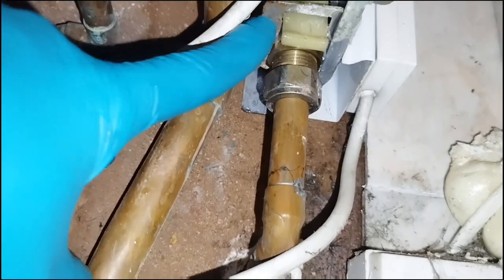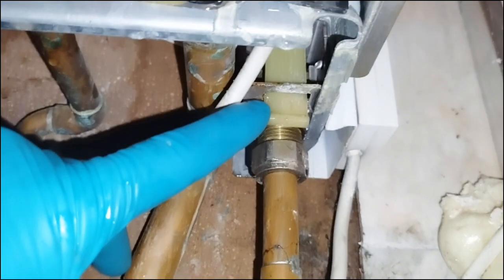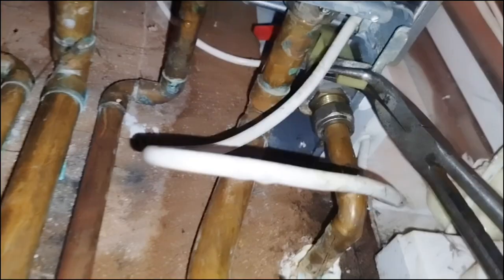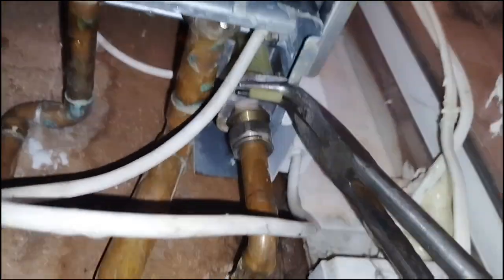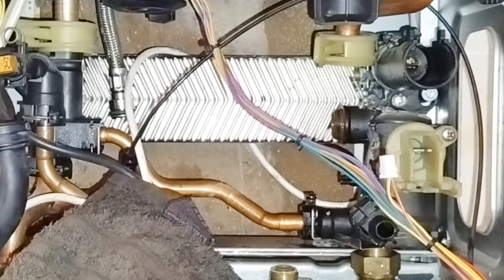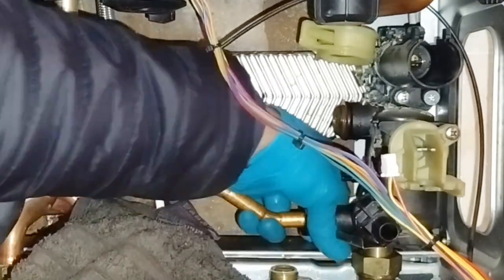Okay, and then we'll pull on the little lever in order to release the PRV. Pull it down, wiggle it, jiggle it, and pull it down with a bit of force so the PRV gets released from that little connection. Further loosened up the return nut from the heating pipe, levered the whole return assembly upwards in order to release it. You can see that I've pushed the plate.